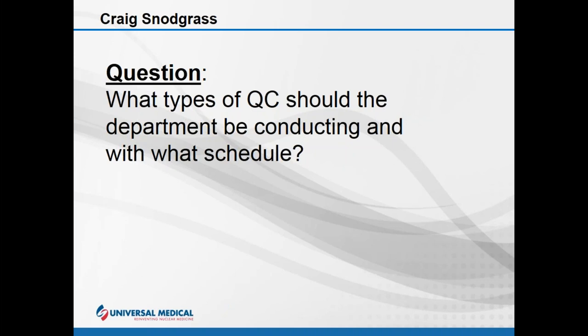Another item that comes from being trained and knowing the specific system is knowing how to check the peak or the spectrum on your detectors. That way, if you see variances in your QC numbers, one of the first things you should check is your peak.